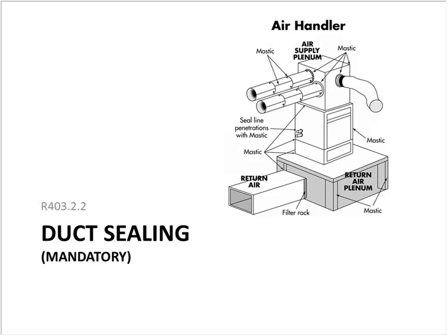And also, in addition to that, there was no evidence presented that using mechanical ducting on the cold air return side was cost effective. So even though it's written in the code that you can't, a ruling has come out that says yes, you can. So that was a quick changeover for the industry, and I don't know if it was for the better as far as indoor air quality and overall performance, but it is what it is. So you do not have to hard duct.